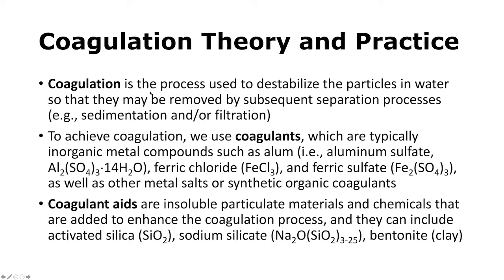Coagulation is the process used to destabilize particles in water so that they may be removed by subsequent separation processes such as sedimentation or filtration. To achieve coagulation, we use chemical coagulants, which are typically inorganic metal compounds. Some examples are alum, ferric chloride, ferric sulfate, as well as other metal salts or synthetic organic coagulants. We may also add coagulant aids — insoluble particulate materials and chemicals that enhance the coagulation process — such as activated silica, sodium silicate, and bentonite clay.